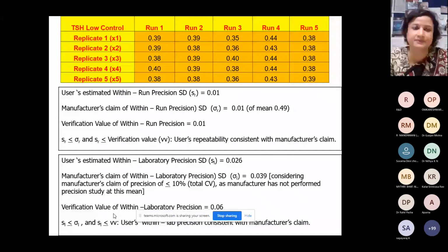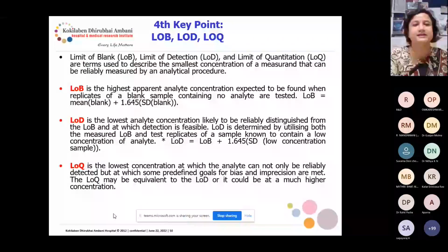Then the user estimates the within-run precision, that is SR, and the manufacturer's claim for within-run precision, that is sigma R, and you calculate the verification value. If SR is less than sigma R or SR is less than the verification value, then you say that the user's repeatability is consistent with the manufacturer's claim. So now coming to the limit of blank, limit of detection, and limit of quantitation.